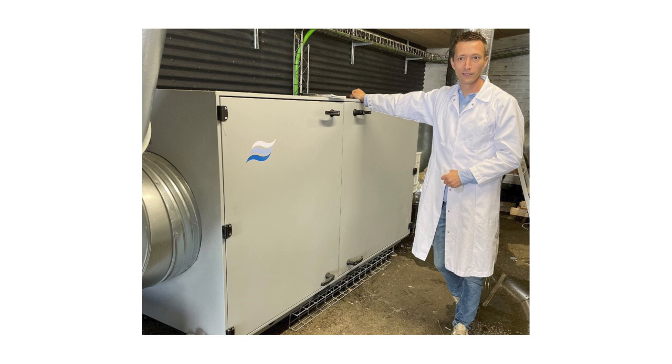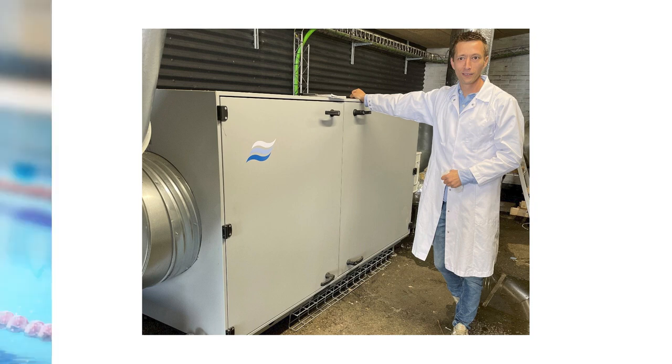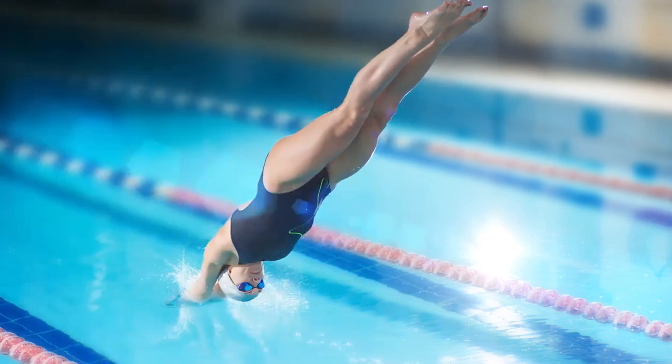And how about the water coming from inside? Yeah, indeed. It's a good point. Any internal sources of water must then be factored in as well as the external sources. For instance, if the area is a swimming pool, then the internal load will be significant. The pool volume, the water temperature, and the hours of operation will help calculate the amount of evaporation. Now, people also give off water, and we do so at varying levels depending on our level of activity. Again, a quality dehumidifier manufacturer will be able to help with these calculations. But to do so, some specific details like the ones I've mentioned need to be determined.